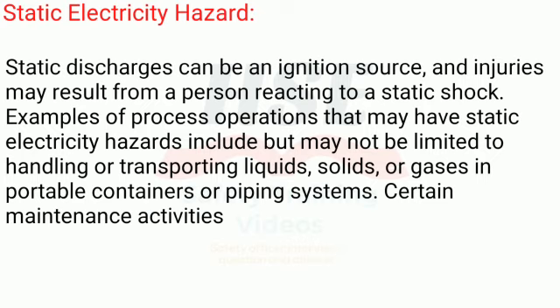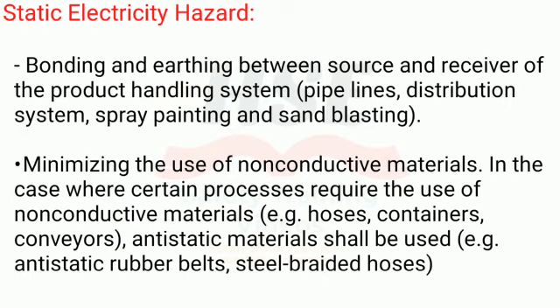Static electricity hazard. Static discharges can be an ignition source, and injuries may result from a person reacting to a static shock. Examples of process operations that may have static electricity hazards include, but may not be limited to, handling or transporting liquids, solids, or gases in portable containers or piping systems. Certain maintenance activities. Bonding and earthing between source and receiver of the product handling system, pipelines, distribution system, spray painting and sandblasting. Minimizing the use of non-conductive materials.